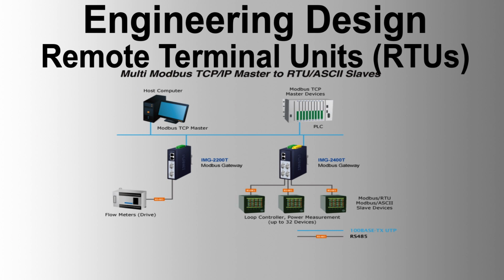Environmental conditions: RTUs are designed to operate in a temperature range of -20 degrees Celsius to +60 degrees Celsius and are suitable for storage from -20 degrees Celsius to +80 degrees Celsius. They meet local requirements for noise immunity and emissions. Security: RTUs have two types of security: programming and configuration interface security with multiple user access levels, and configurable access levels for each RTU communication port to control read and write access.